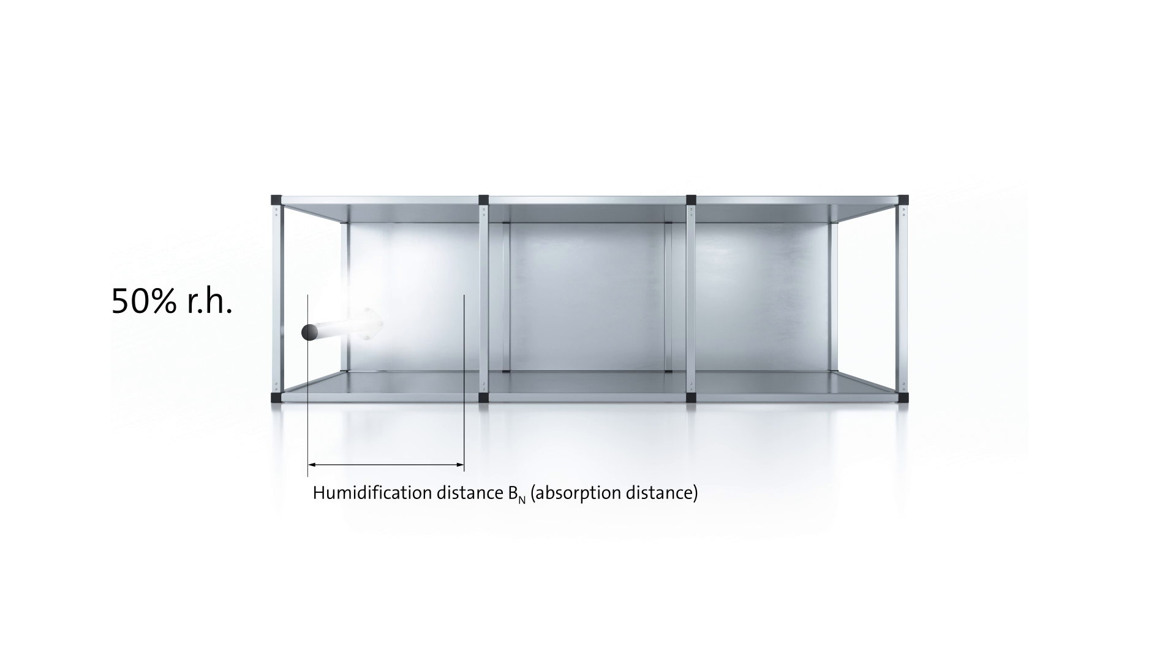The humidity of the air is also relevant because the higher the humidity of the air, the lower further humidity absorption by the air becomes. Consequently, if the air is very humid, say at 80% relative humidity, a longer humidification distance BN needs to be provided. Vice versa, at only, say, 30% relative humidity, a shorter distance is required.